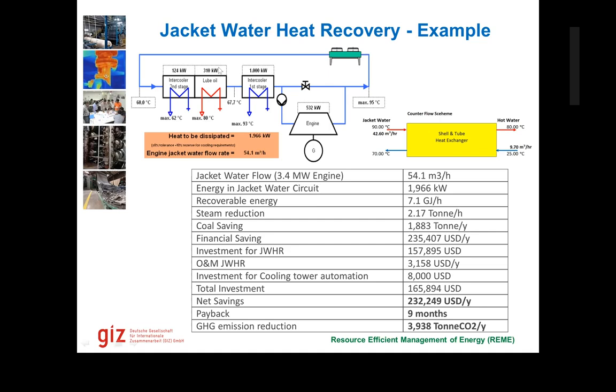So this is a flow diagram that is provided by the equipment manufacturer of a 3.4 megawatt engine running on natural gas, and it shows different areas where the heat is dissipated. So this is the water cooling cycle, this blue and red, and all this cycle is going through the cooling towers. And what we did was we did a calculation for a jacket water heat recovery system, and you can see that the payback is only 9 months, because it would significantly reduce the amount of steam required in the processes, and also increase the process output.